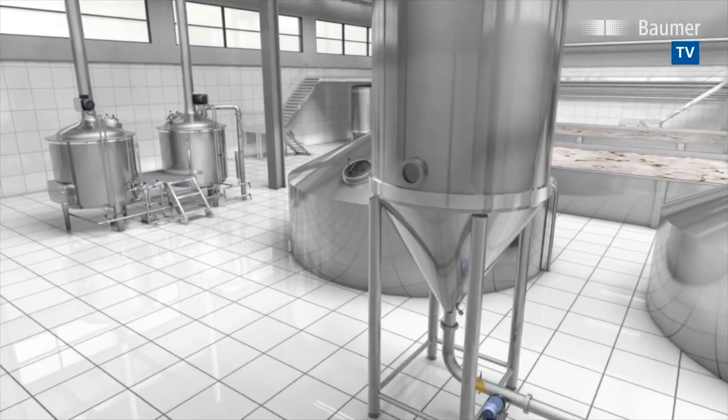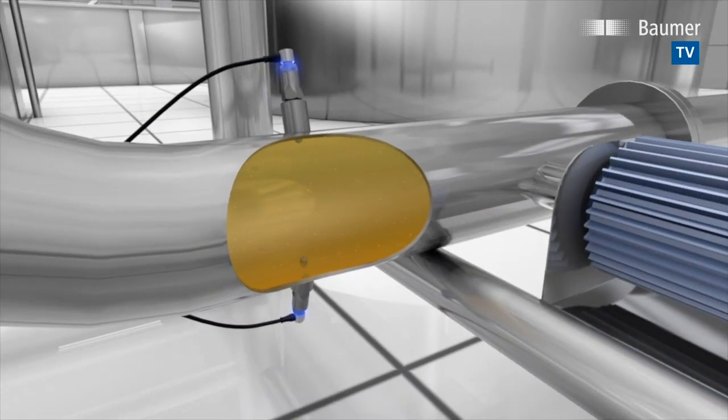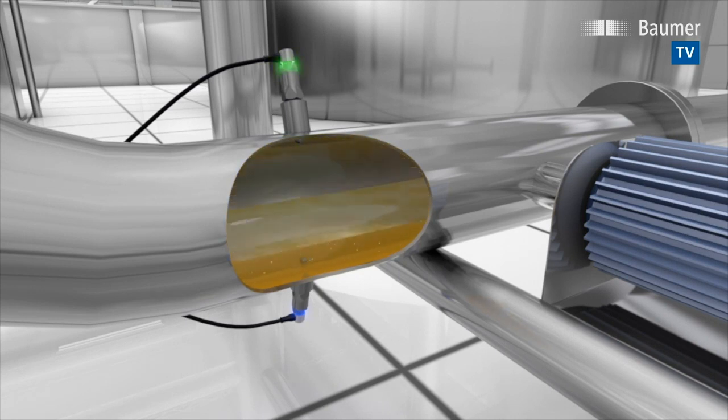In breweries, Clever Level switches are deployed for empty pipe monitoring. Installed at the pipe's top end, Clever Level will trigger a switching output as soon as the fluid no longer fills the pipe completely.